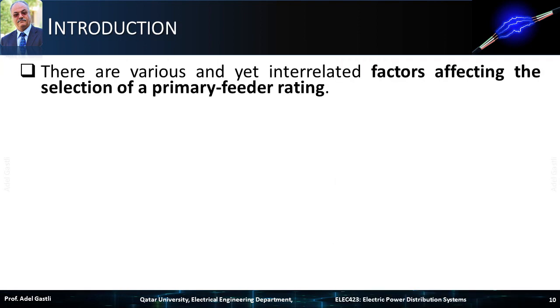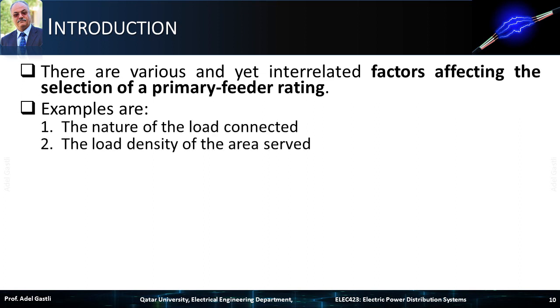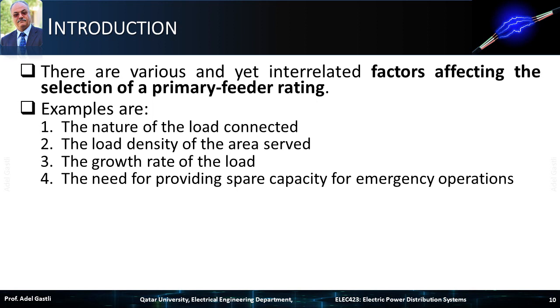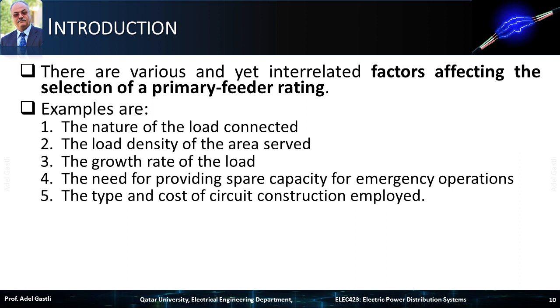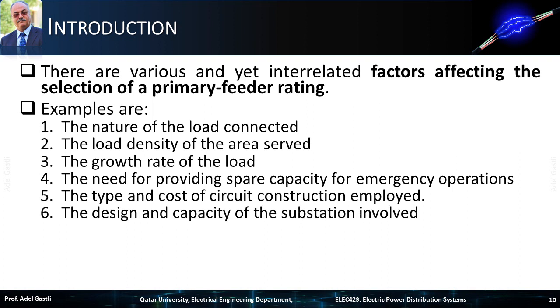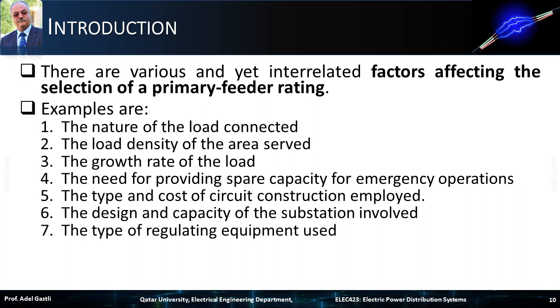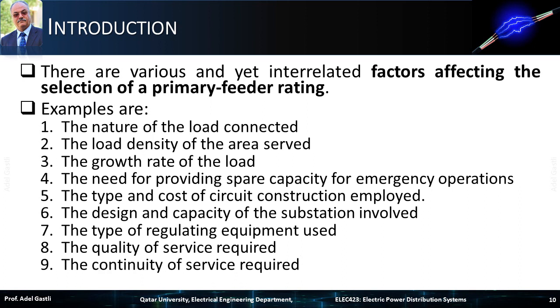There are various and yet interrelated factors affecting the selection of a primary feeder rating. Examples are: the nature of the load connected, the load density of the area served, the growth rate of the load, the need for providing spare capacity for emergency operations, the type and cost of circuit construction employed, the design and capacity of the substation involved, the type of regulating equipment used, the quality of service required, and the continuity of service required.